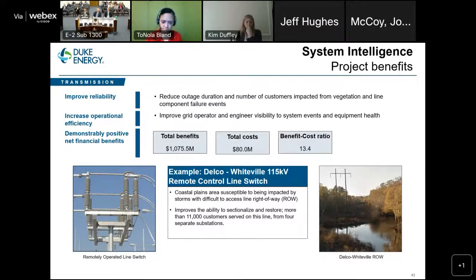We are deploying more remote-operated switches, both in new locations and by upgrading manual switches. This gives grid operators the capability to make switching manipulations remotely from the control center. Combined with digital relays that pinpoint fault locations, we go from resolving a transmission outage in hours to resolving it in minutes.